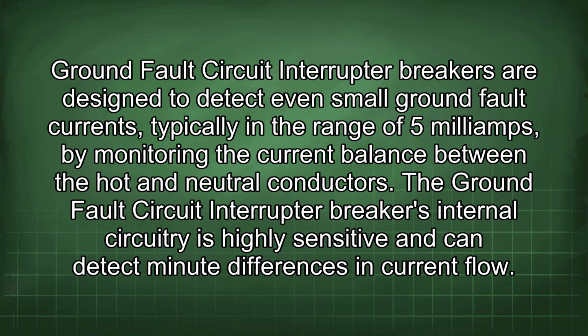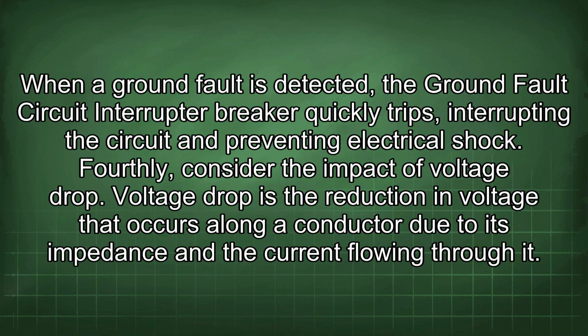Ground fault circuit interrupter breakers are designed to detect even small ground fault currents, typically in the range of 5 mA, by monitoring the current balance between the hot and neutral conductors. The ground fault circuit interrupter breaker's internal circuitry is highly sensitive and can detect minute differences in current flow. When a ground fault is detected, the ground fault circuit interrupter breaker quickly trips, interrupting the circuit and preventing electrical shock. Fourthly, consider the impact of voltage drop.